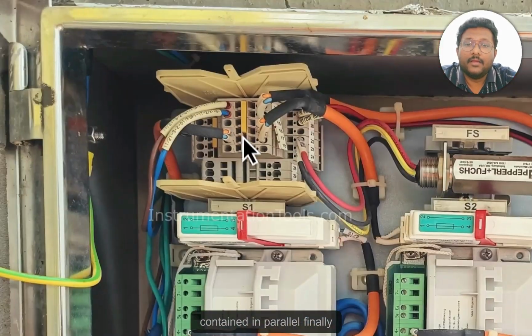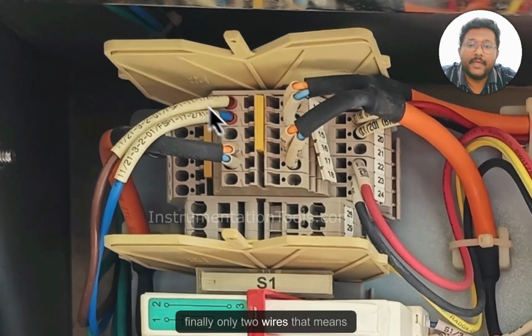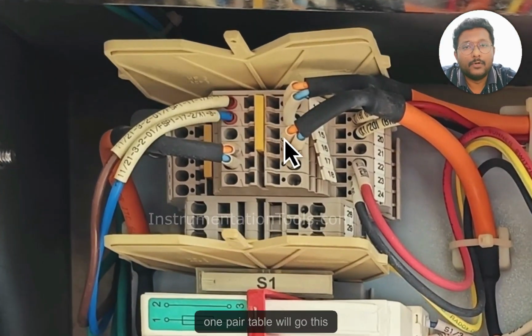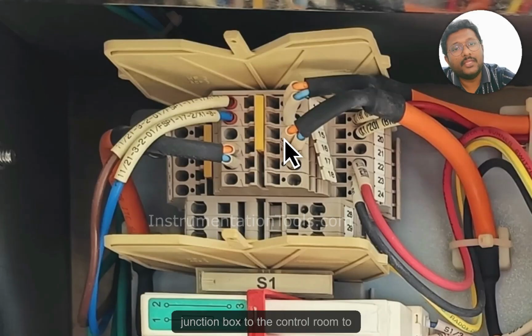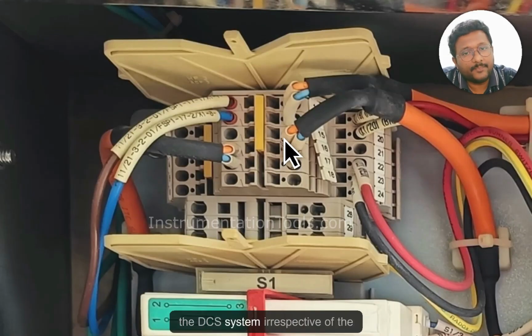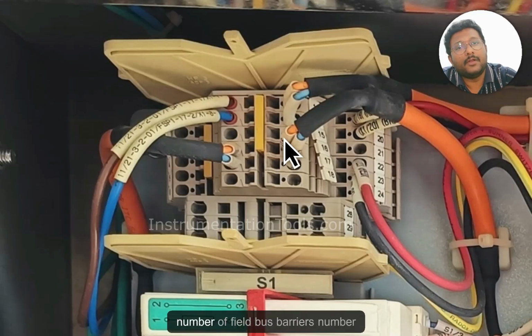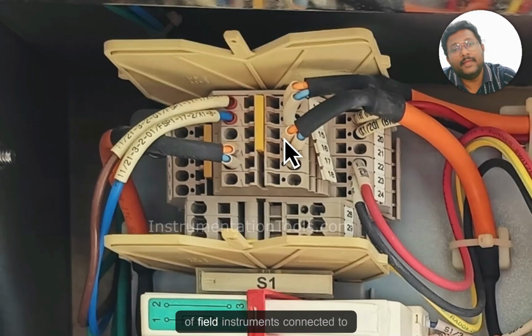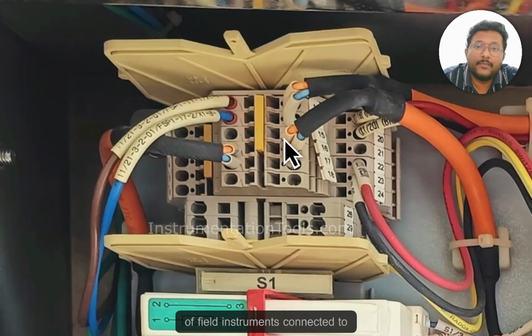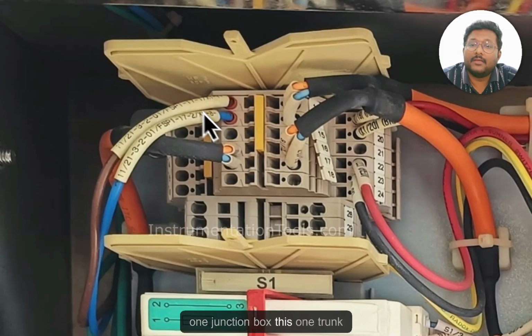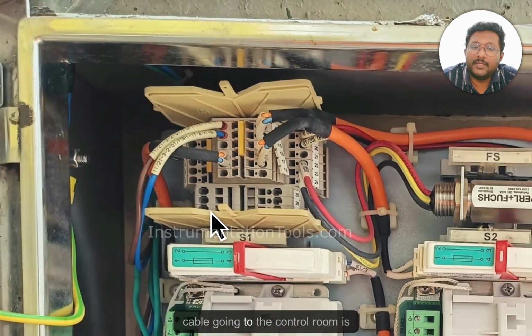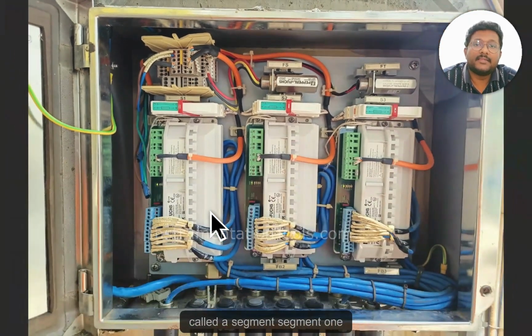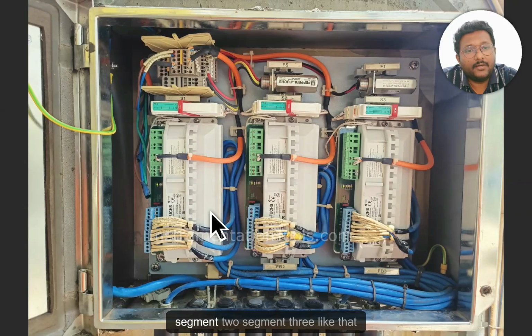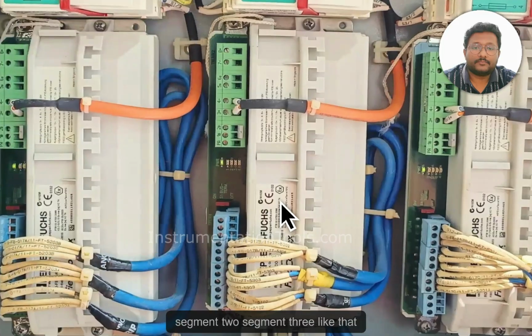Finally, only two wires. That means one pair cable will go from this junction box to the control room, to the DCS system, irrespective of the number of field bus barriers and the number of field instruments connected to one junction box. This one trunk cable going to the control room is called a segment. Segment 1, segment 2, segment 3, like that.